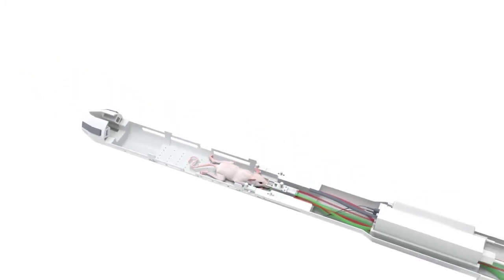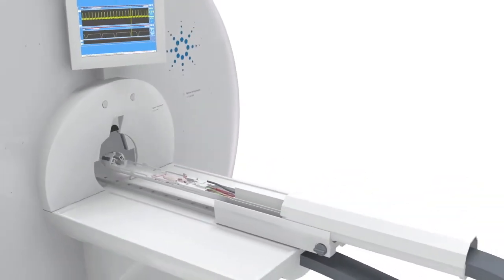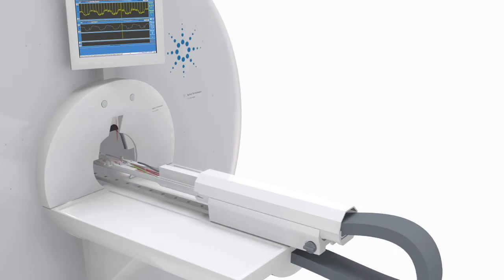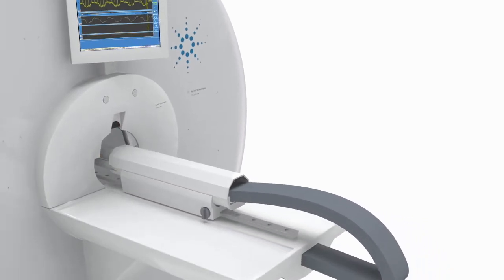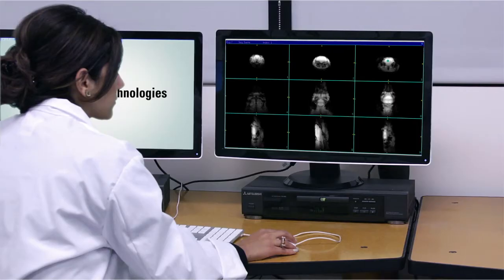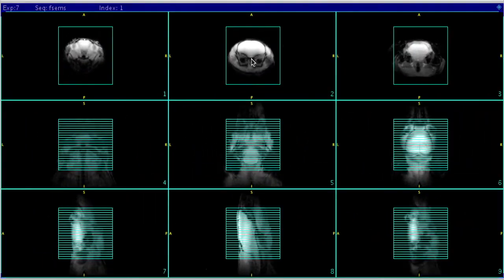Once the specimen has been arranged in the sample holder, it is ready to be scanned. Physiological monitoring can occur using the touchscreen conveniently located at the sample prep table. The ECG, temperature, and respiration sensors are attached to the holder, and the air heater and anesthesia lines connect when the cradle is docked. The laser has a very fine crosshair beam to ensure precise positioning. Once the sample is in the N-Scope eMRI, the touchscreen media and acoustic shielding allows for running a scout scan right at the magnet. Agilent's advanced VNMRJ3 software for fast, intuitive data acquisition has been further optimized to fully enhance the N-Scope eMRI workflow.